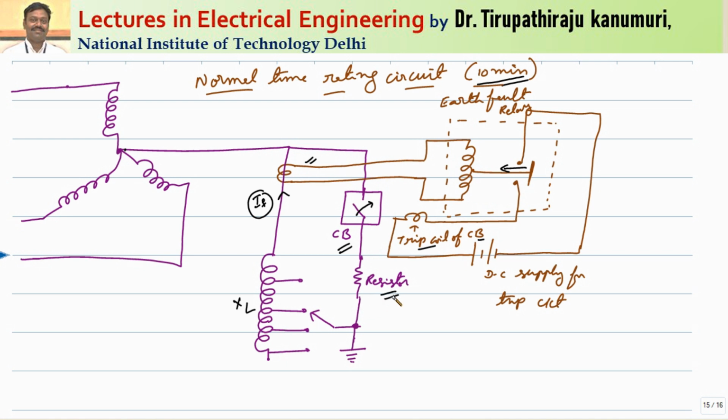So we have seen the resistance grounding, the fault current is more than that of the isolated neutral grounding and less than solid grounding. So the fault current will be more. When the fault current is more, automatically, whenever it switches to resistor, fault current increases. So whichever circuit breaker is connected in the respective phase, let us assume this is my R, Y and B phase, this will detect this fault current and it will isolate that respective phase.